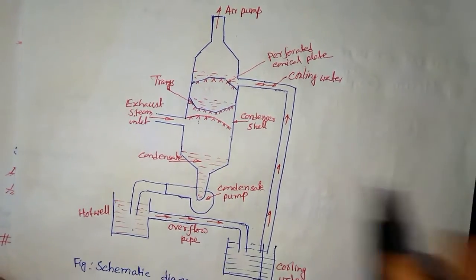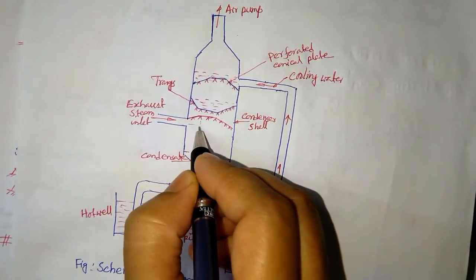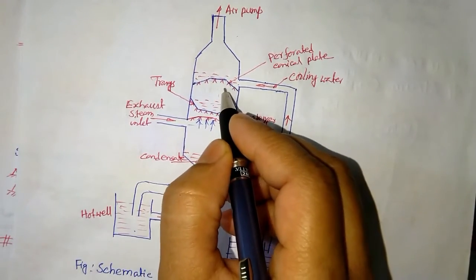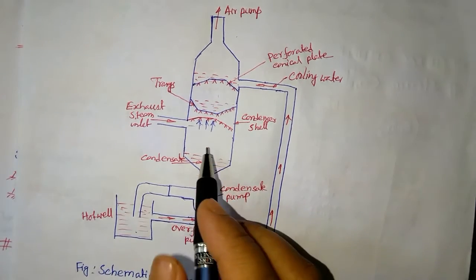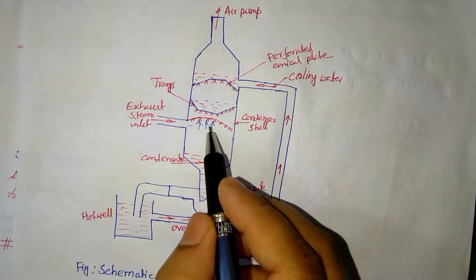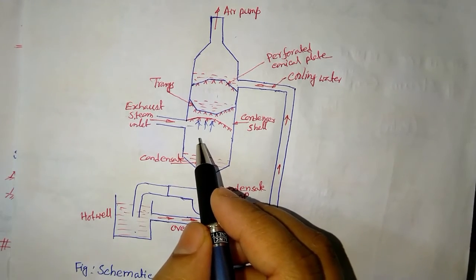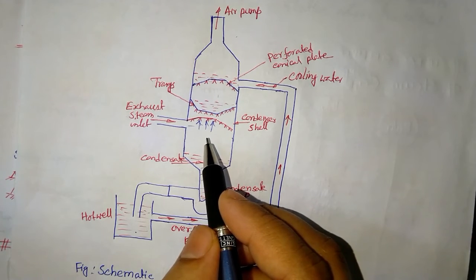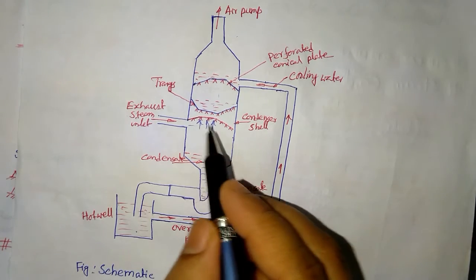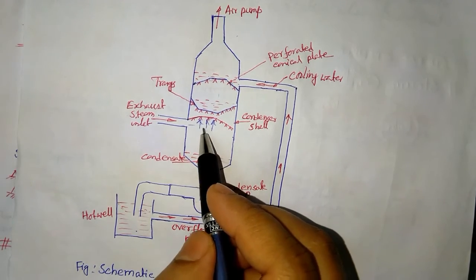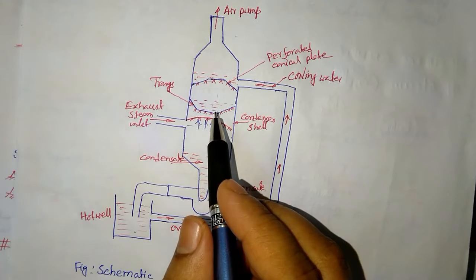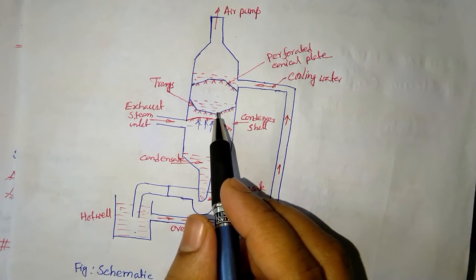Because steam flows upward and cooling water flows downward in opposite directions, this type is called a counter-flow condenser. In some types, steam and cooling water flow in the same direction, making it a parallel flow condenser.